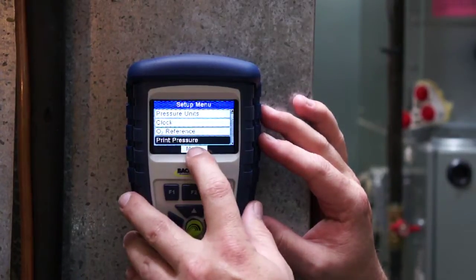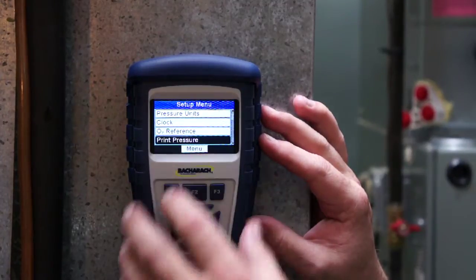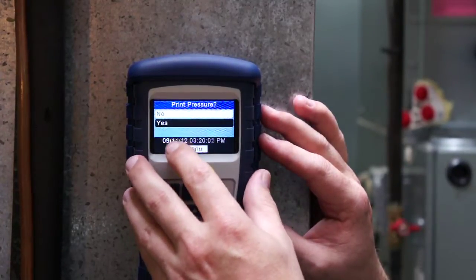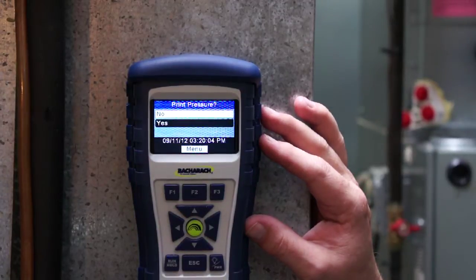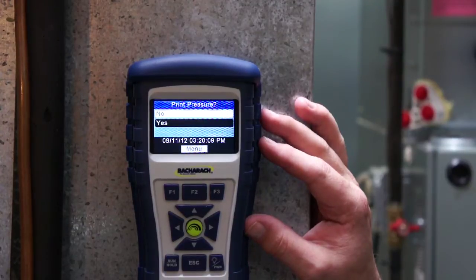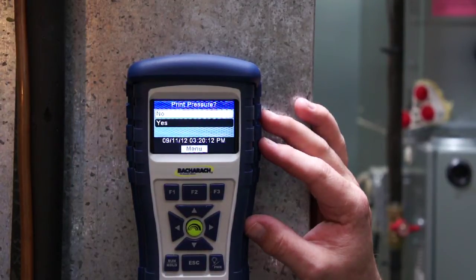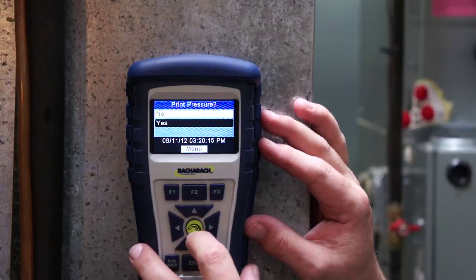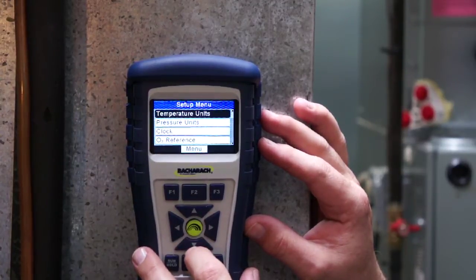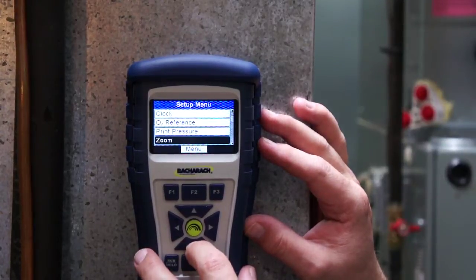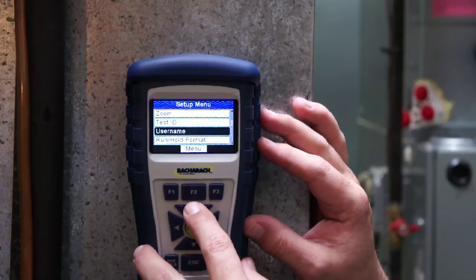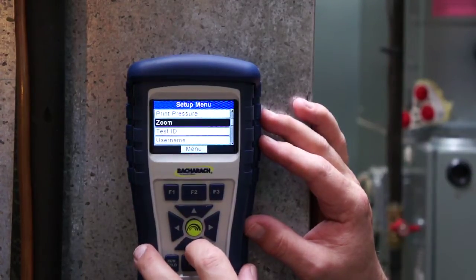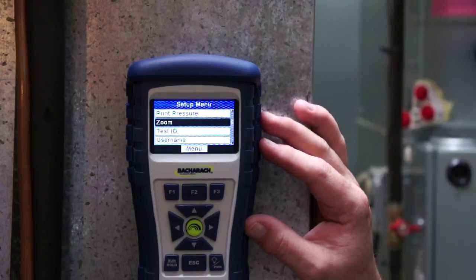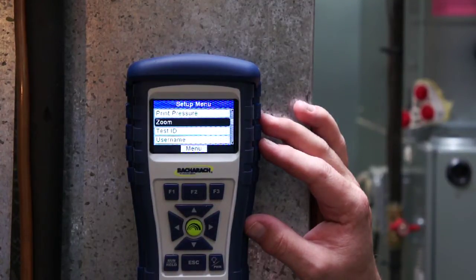I can configure my print pressure, so I can turn it on or off, yes or no. And basically what that'll do for me is if I use the analyzer to measure fuel pressure and I want to print that out, I can print it on the printout with the rest of the combustion readings on the display. So I have that set to yes. And then going down below that here, I've got my zoom and then test ID, username, run hold format. So let's say I want to go in and change my display, because right now it's a 5-line display, and sometimes you're a little bit further away from the analyzer and you want to make it easier to read.